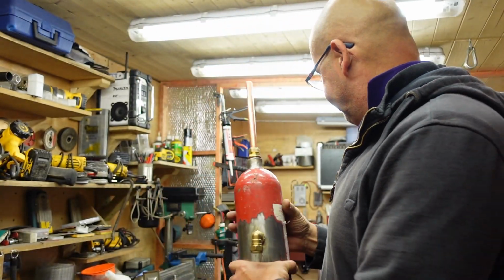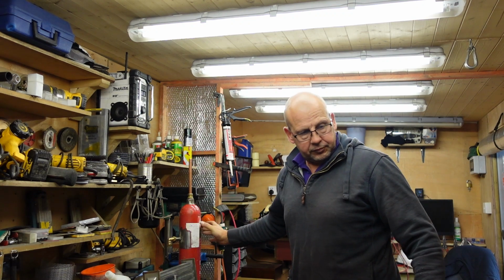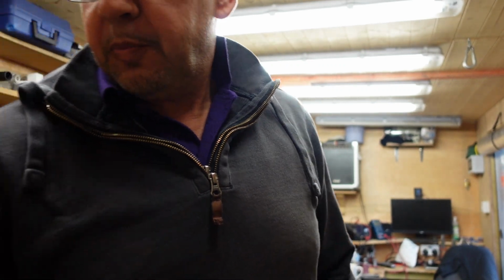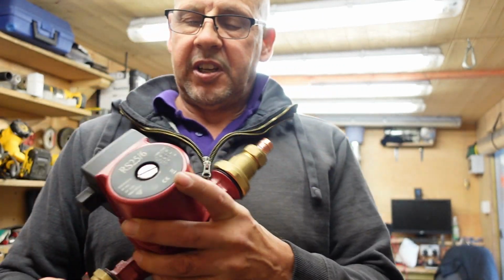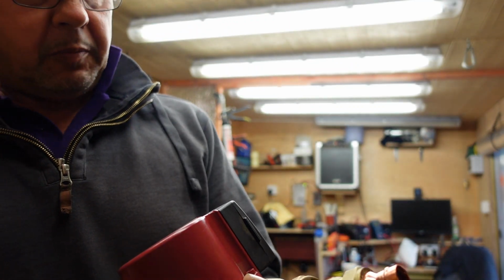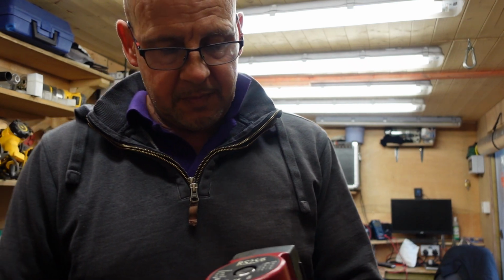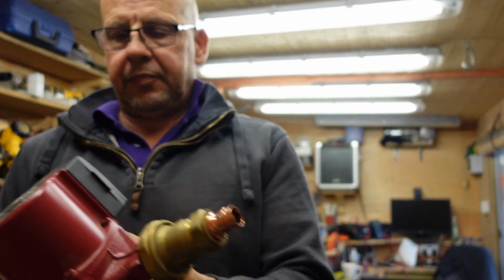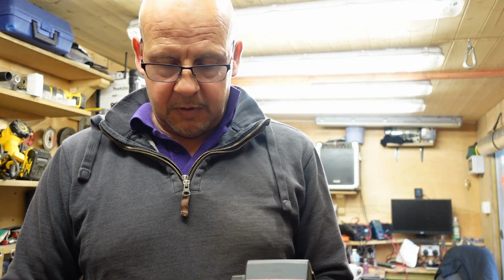Right, what I'm using for a pump to pump it around is a standard 240 volt pump for a central heating system. So it's a 22mm to 15mm coupler on it. I've got to wire it up, but this has got 3 settings. So because I'm using 15mm on the outside, I'm only using a 10mm copper coil, so I'll probably set it on low and see how it goes from there.